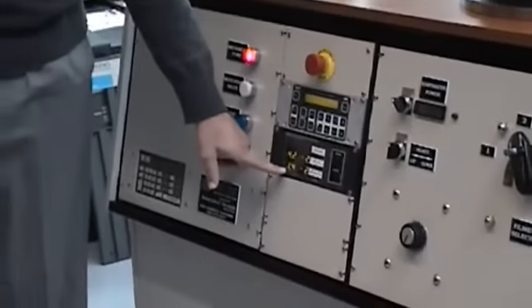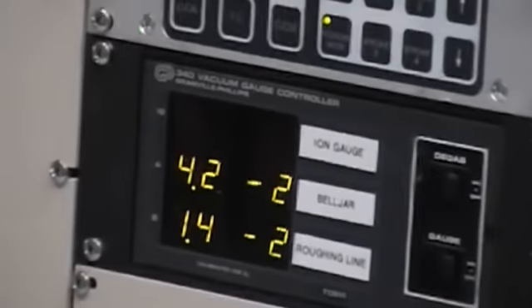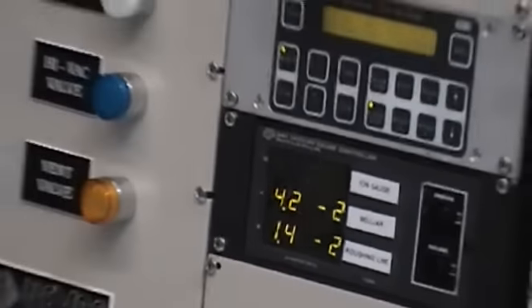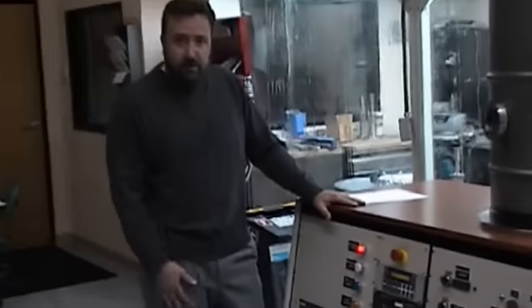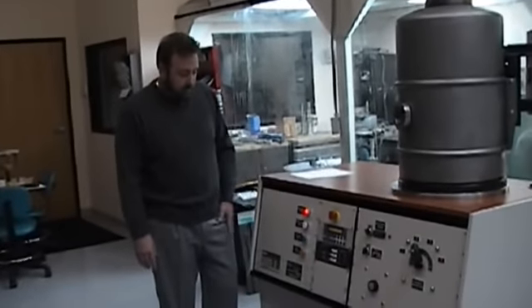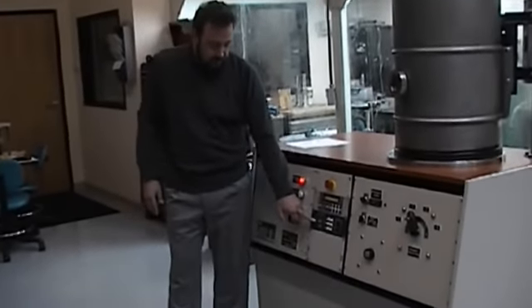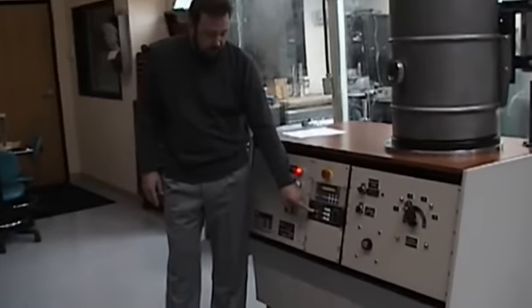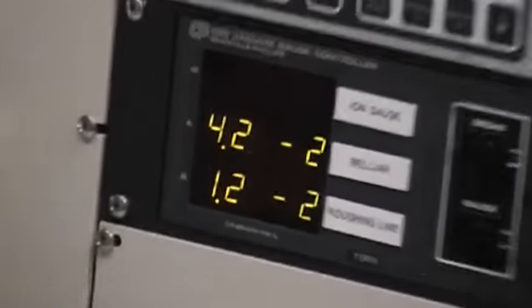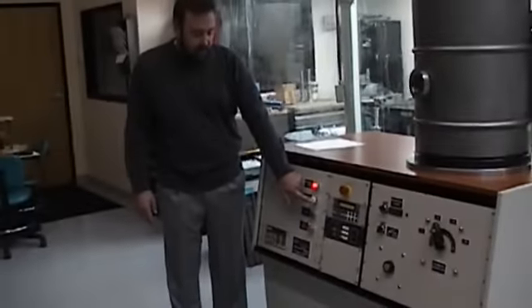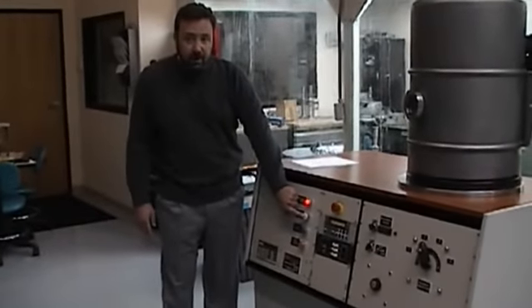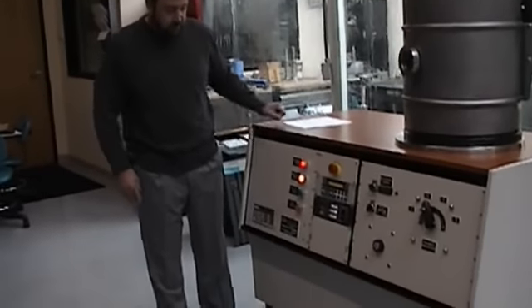As you'll notice, in the roughing line, our vacuum pump has quickly come down to pressure 1.4 times 10 to the -2, roughly 13-14 millitorr. Currently, we have the bell jar at 4.2 times 10 to the -2, which is roughly 42 millitorr. I'm going to go ahead and just demonstrate the opening of the rough valve and bring down the pressure to equal.